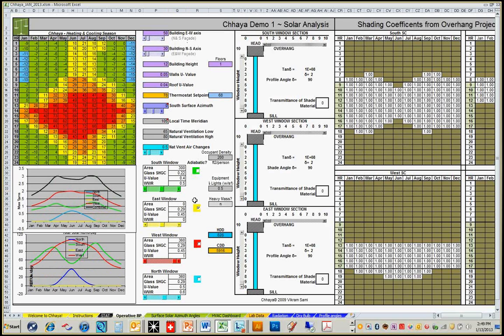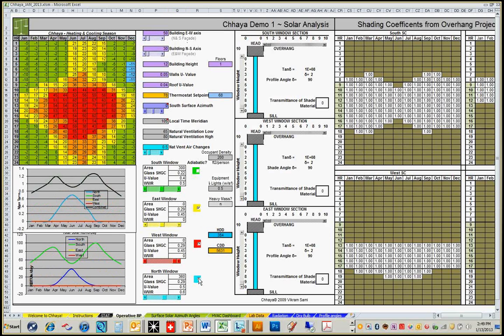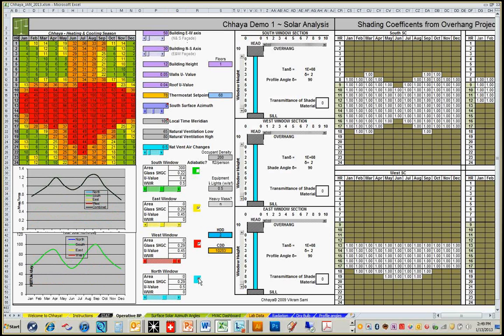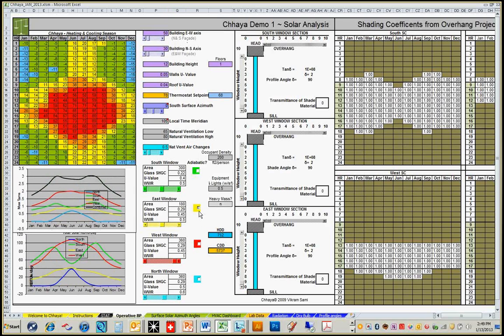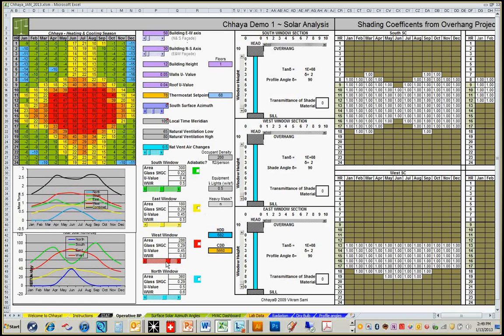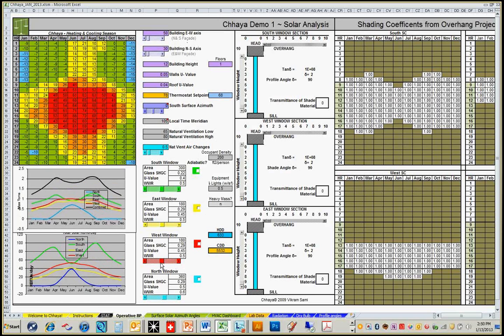As you make your facades adiabatic, it makes it harder to lose heat, so it will actually trap more heat, and you'll see greater overheating. So sometimes it's counterintuitive. You assume that reducing external exposure reduces your heat gain, but it also reduces your heat loss. So that's something to keep in mind.